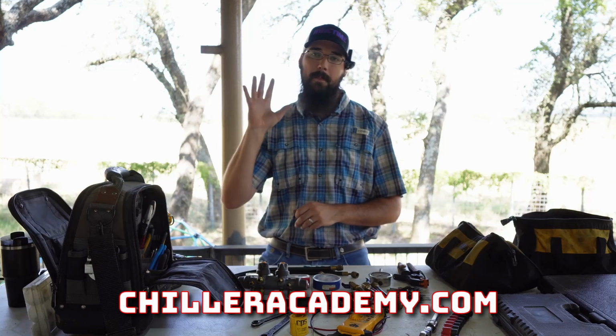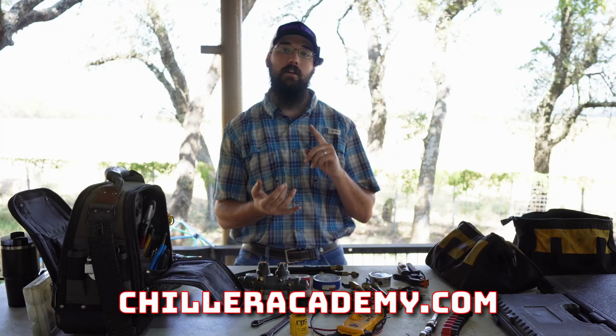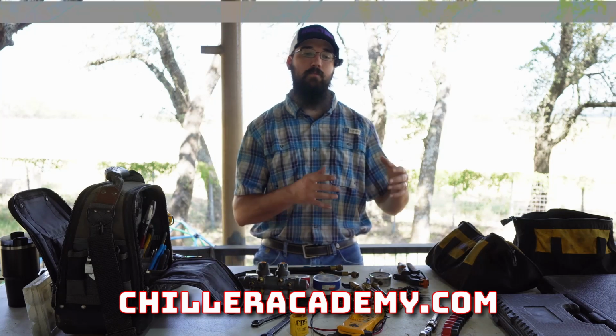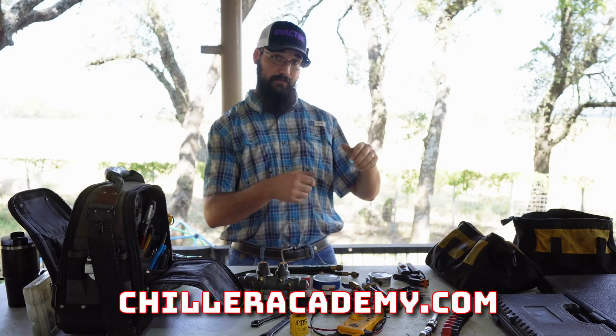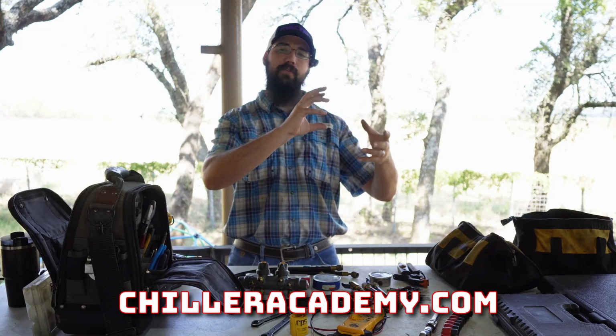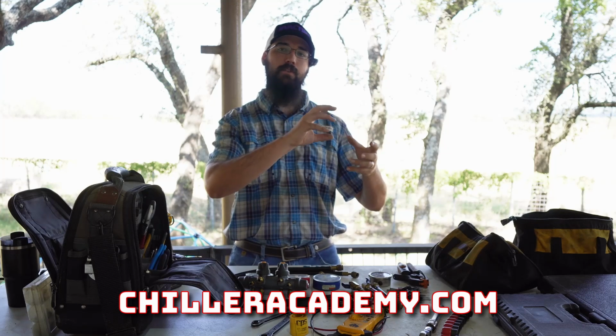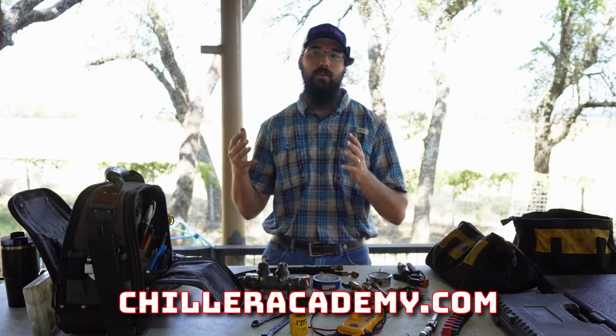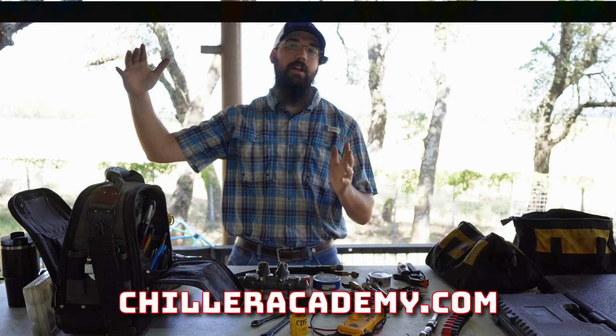No. So an electrical supply house specifically. In my area, I could go to Summit Electrical Supply or Elliott Supply. Either of those, you can get a large set of crimpers. The ones I'm referencing, you could get them where there were 4 or 5 different sizes in one crimper set, and you would just rotate a set of heads on the crimpers to pick your size, and then you're going to have the fitting that fits that. So if you're ever having to do lead replacements on these large compressor motors and such, you're going to need a set of crimpers like that.